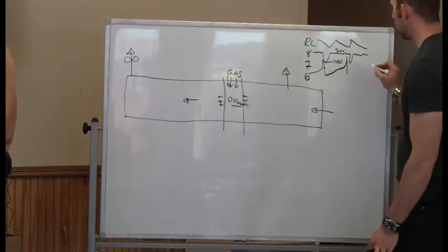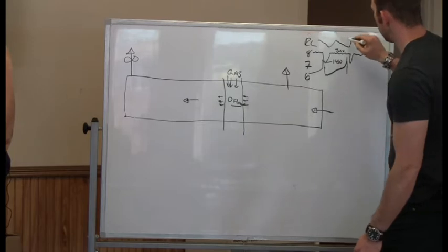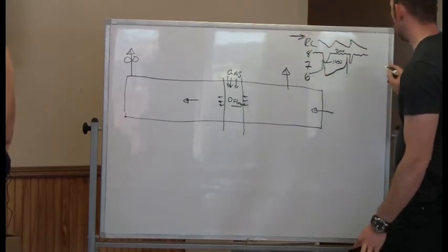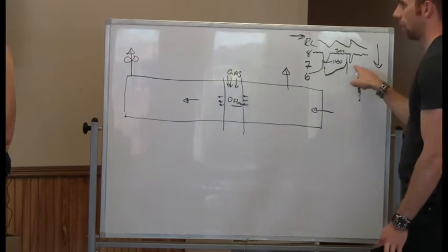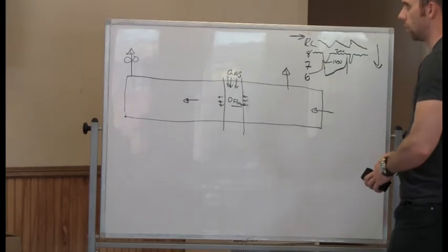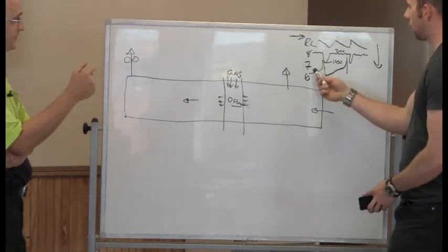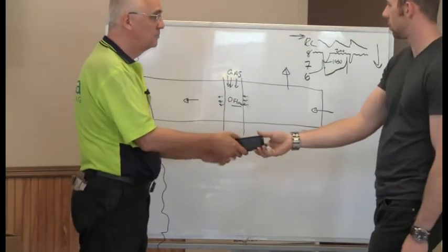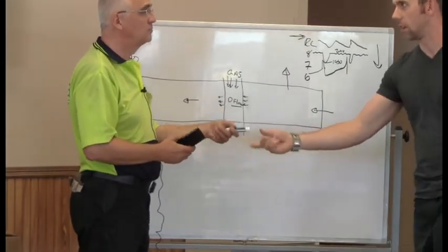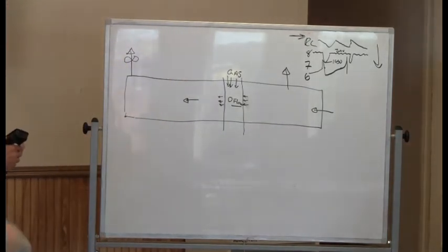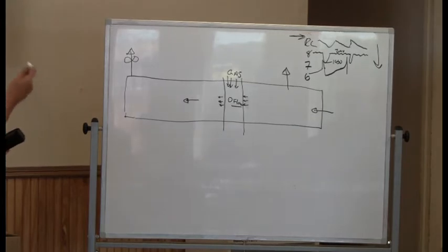So basically, we're no longer backdrafting into here, and the fuel is actually going down the tunnel and igniting into 7. That's what you're looking for. Actually, I even had a bit written in the program to keep this from going crazy, so that as soon as this goes over temp, everything is cut off, airflow and gas-wise, in the burner group. We'll talk about the burners and stuff like that after.